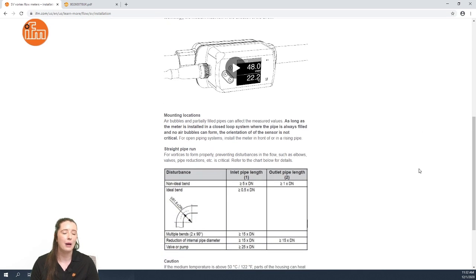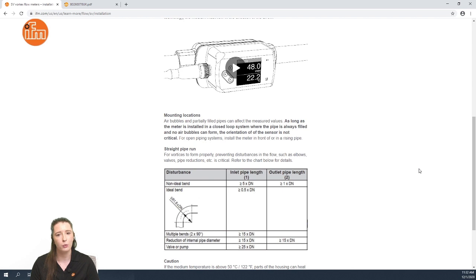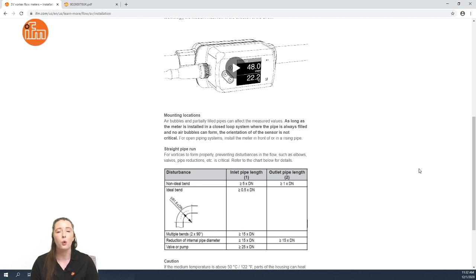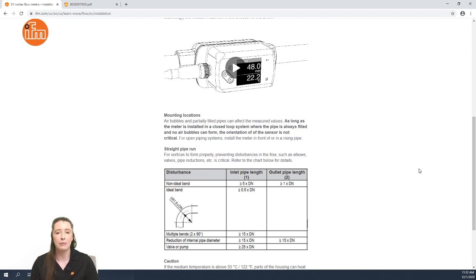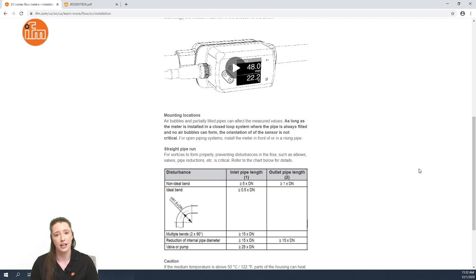Next we talk about mounting locations. In a closed-loop system where the pipe is always filled and there are no air bubbles that can form, the orientation of the sensor is not critical. However, in an open piping system, it is recommended that the sensor be mounted in front of or in a rising pipe.